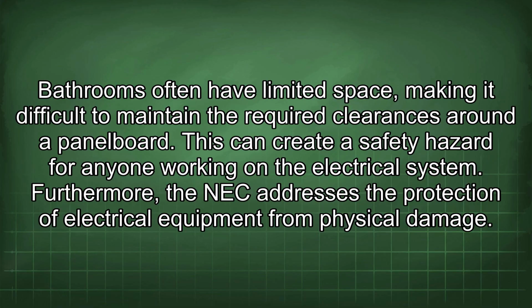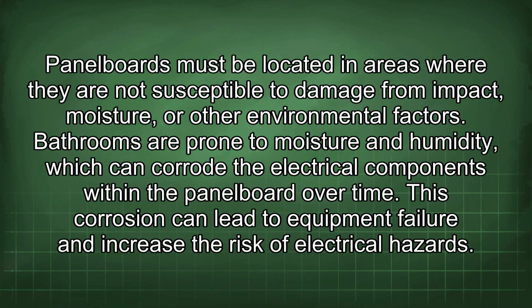Furthermore, the NEC addresses the protection of electrical equipment from physical damage. Panel boards must be located in areas where they are not susceptible to damage from impact, moisture, or other environmental factors. Bathrooms are prone to moisture and humidity, which can corrode the electrical components within the panel board over time. This corrosion can lead to equipment failure and increase the risk of electrical hazards.